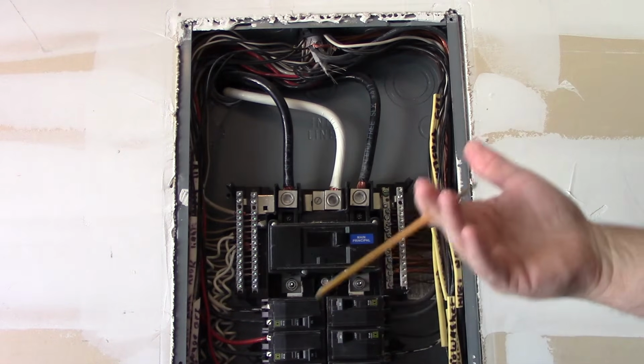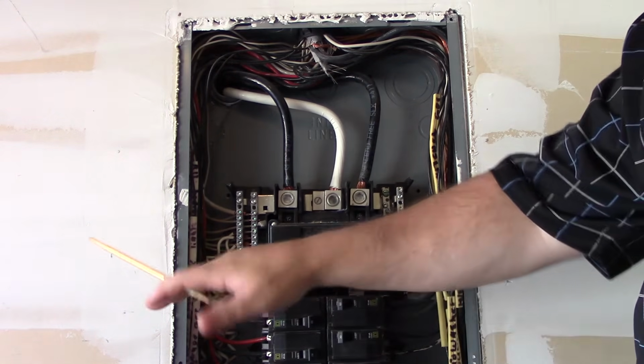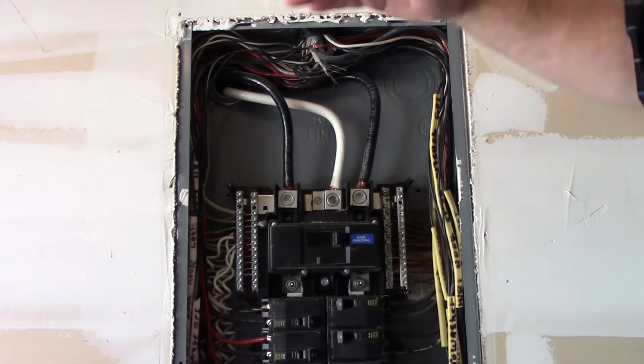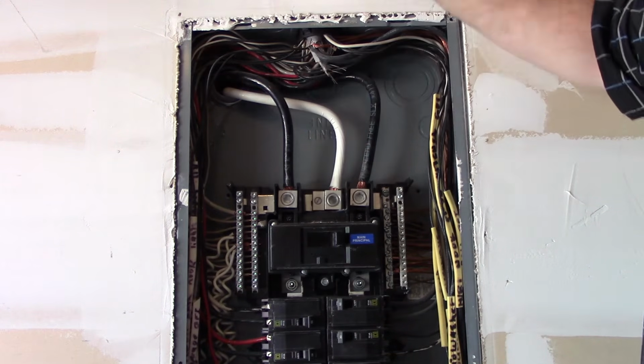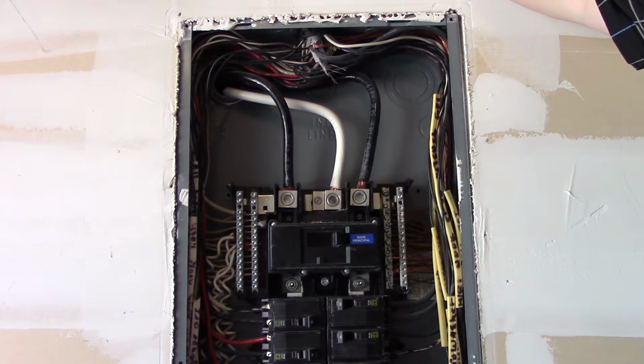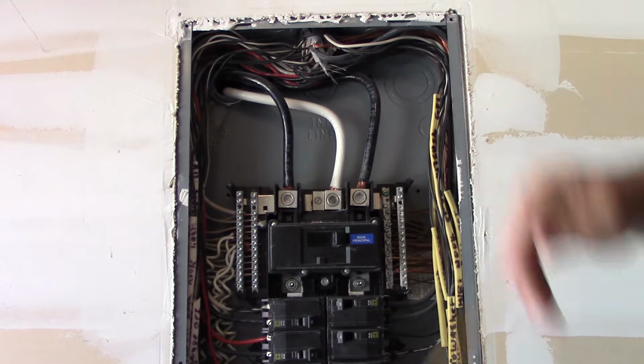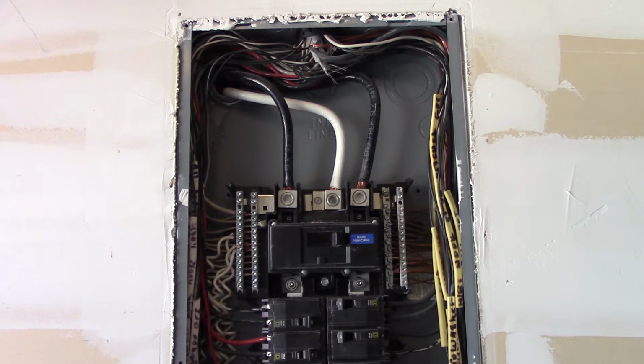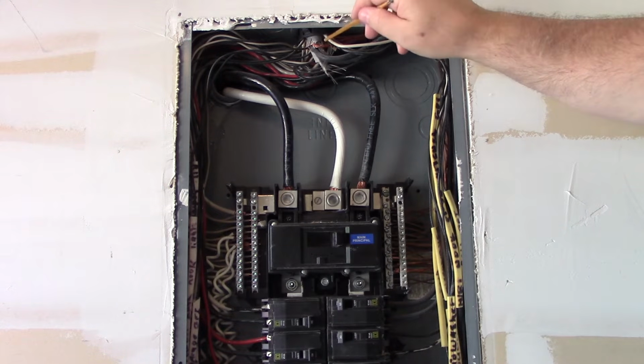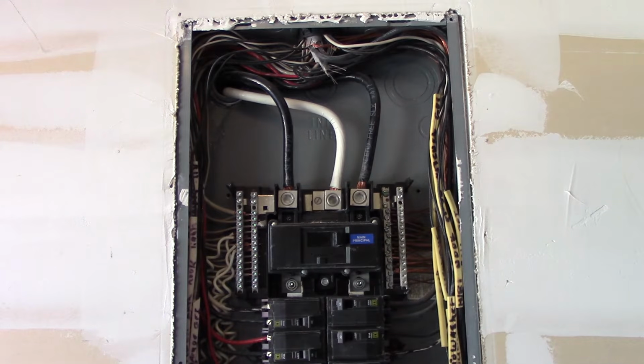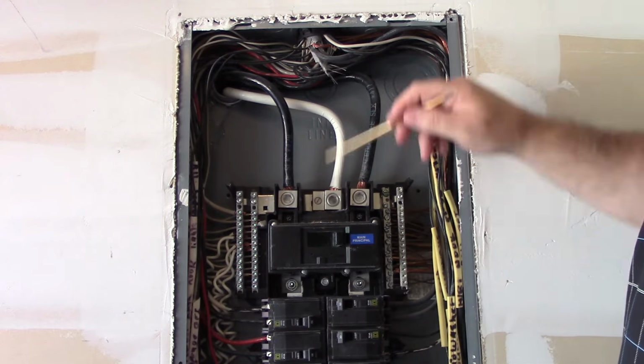Now, there is an exception to this rule. If this was a surface mount cabinet and the raceway that these cables came into was at least 18 inches long and no more than 10 feet, and all those cables were secured within 12 inches of exiting that raceway, and it was sealed at the end, then I can get away with that, although I do have to worry about bundling issues, and we do have allowances in the code that deal with that. But in this case, as a municipal inspector, I'm going to call this out because this is a violation of 312.5(C).